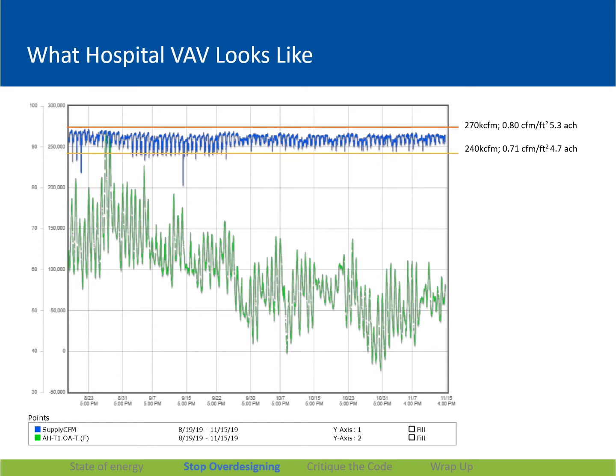This picture is real data. This is from one of our hospitals. It's a hospital that's 340,000 square foot, and I'm showing you September to November. So you can see the outside air temperature ranges between 90 degrees and 40 degrees. The design capacity of this system, of all the air systems in the building, is 350,000 CFM. That's about 1.0 CFM per square foot, or 7 air changes if you want to call it that. And that includes a margin of safety, as design always does. So you can see that on a 90-degree day, we do not need all that air. We're only using 270,000 CFM, which is 0.8 CFM a square foot, or 5 air changes.